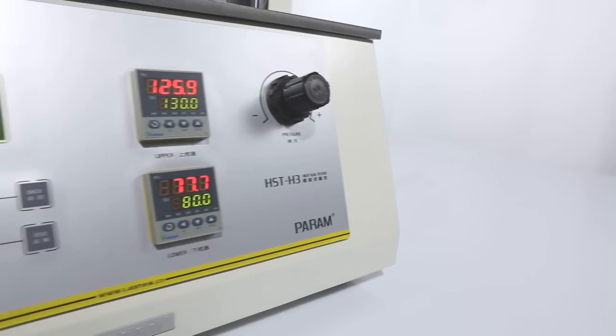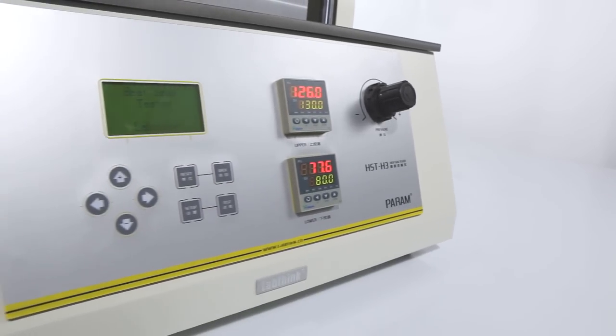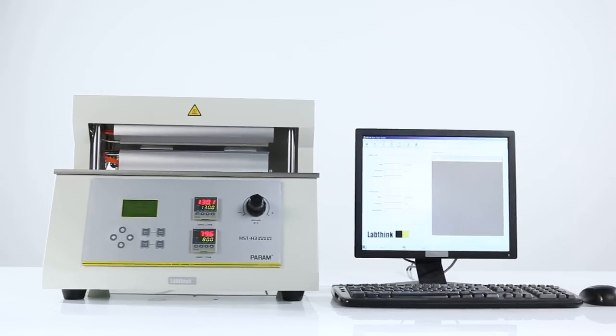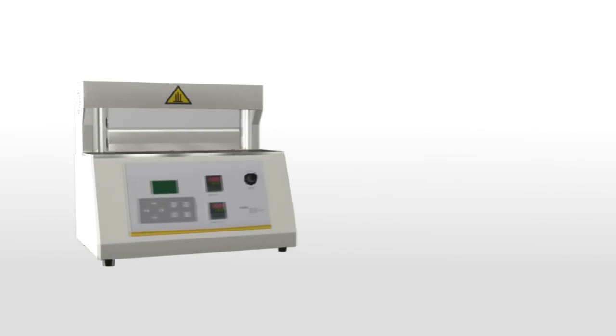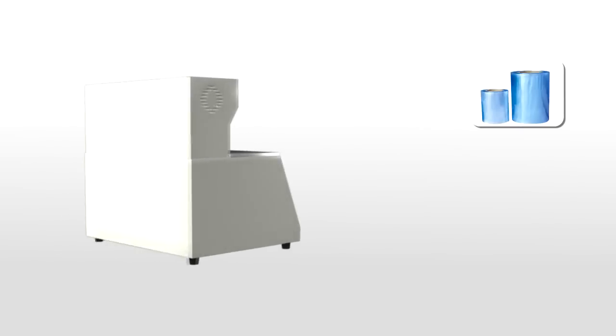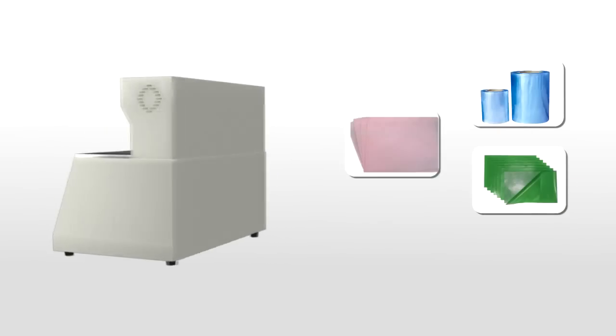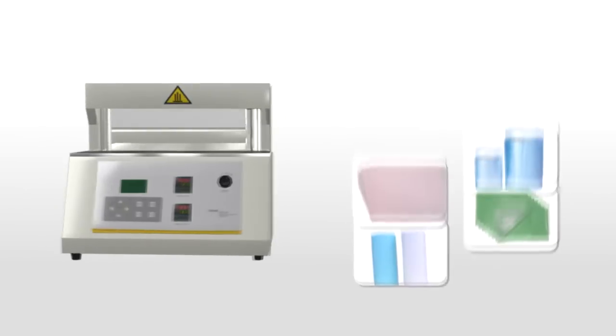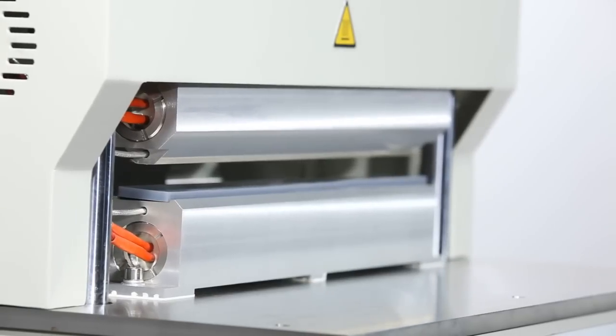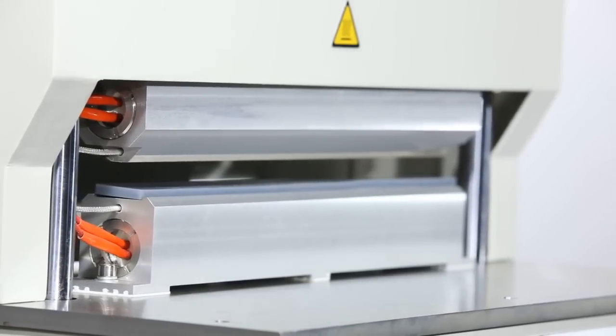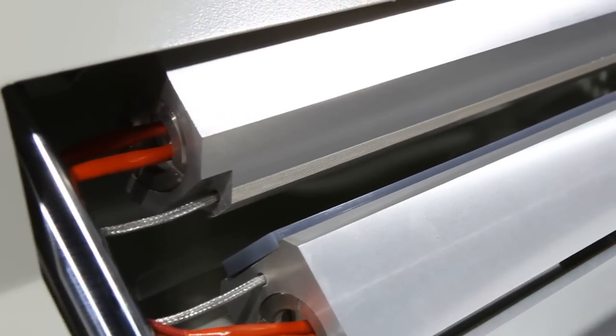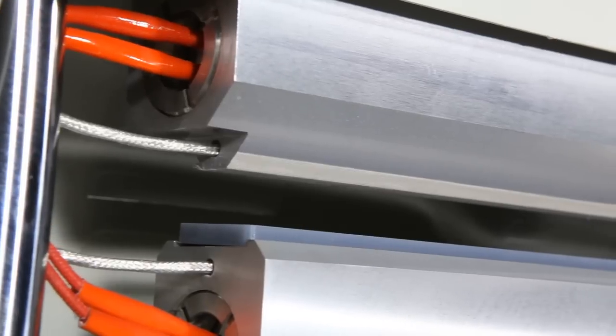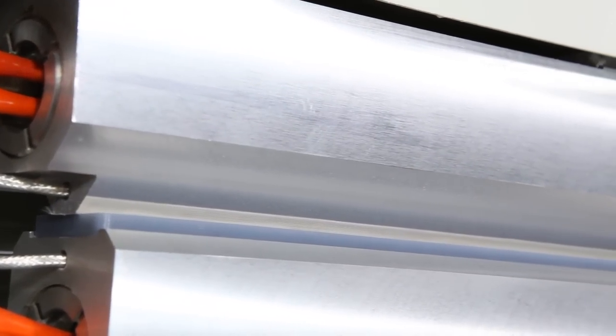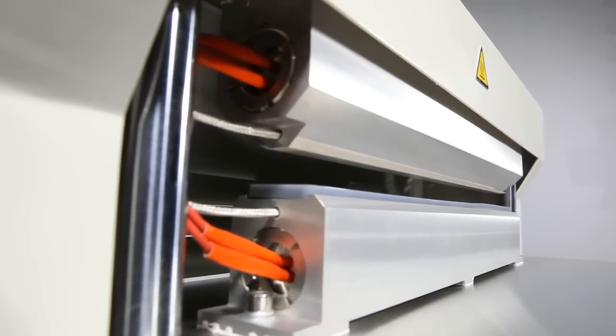HST-H3 is Labthink's best-selling heat seal tester, which is used to determine the heat sealability of flexible webs such as basic films, laminated films, coated paper, and other heat-sealing laminated films. Independent temperature control of the upper and lower jaws of the heat sealer and the aluminum encapsulated heating tubes ensure an even temperature along the sealing jaws.